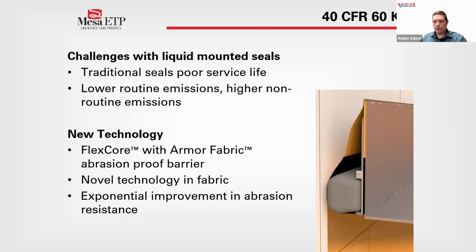When you drain and degas this tank, you still have product in that foam, which is problematic. So traditionally, these foam seals have used urethane fabric. And with that, we would expect the life expectancy to be about 3 to 5 years.